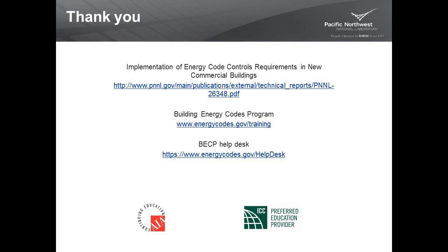Okay, this is two questions in one. Was the field study conducted on buildings that had commissioning done, and were different buildings studied at different points of post-construction, for example, within 1 year post-construction? I think I answered the second question already. It varied. We tried to make it as close to post-construction as possible. Some of the buildings were commissioned and some weren't, and we collected that data and tried to do some statistical correlations there as well. In most cases, there just wasn't enough data to come up with anything really meaningful. We were hoping we could say, hey, commissioning really helps these controls out, and in some cases we were able to show a relationship that it was better. We did it on a measure-by-measure basis, and we looked at it by HVAC and lighting, and there are some details on that in the report as well.